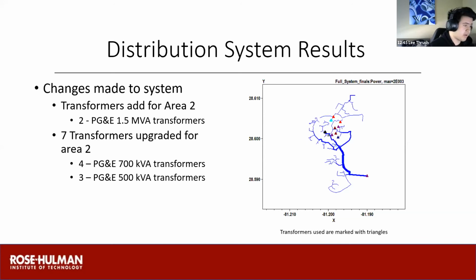Ultimately, we chose to upgrade transformers over downsizing our system or introducing more batteries, because we found that it was the most optimal solution for what we wanted to do. We did not want to change our energy offset to have it decrease. And if we wanted to keep the same energy offset and have batteries, we found it would be much too expensive to implement. In addition, it would increase our hosting capacity, so after the lifetime of our system, if we wanted to upgrade our system, we could do that and likely not have to upgrade transformers again.